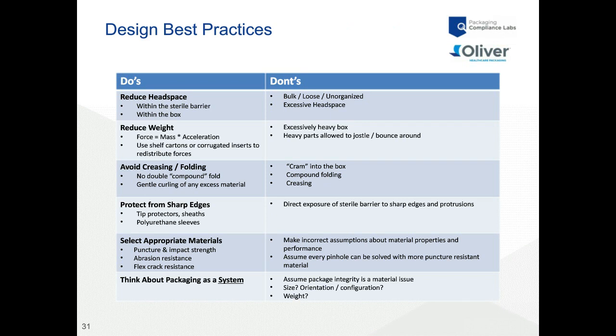And a side comment with respect to open seal defects: there can be many different root cause scenarios. This is one that Ryan highlighted with respect to drop, but you also have to consider things that can happen during EO sterilization cycles, when temperatures are elevated and there's a lot of pressure involved getting the gas in and out. Those can be treacherous environments for seals, so open seal root cause analysis should always include your EO cycle. It can include transportation in warm climates, altitude, and things like that.